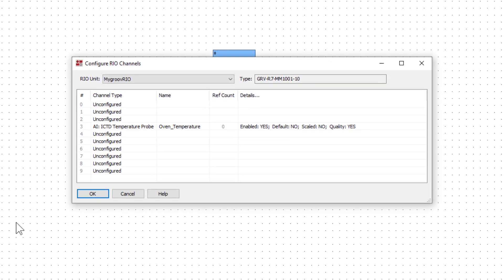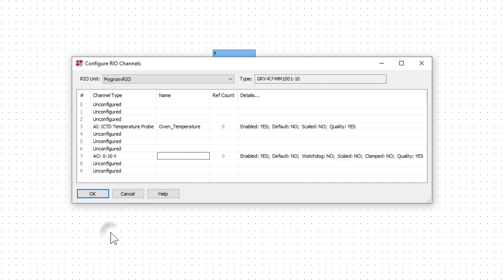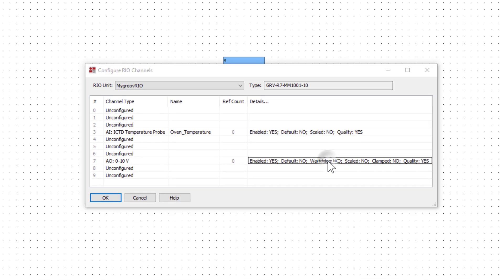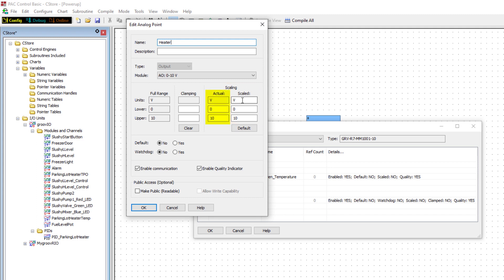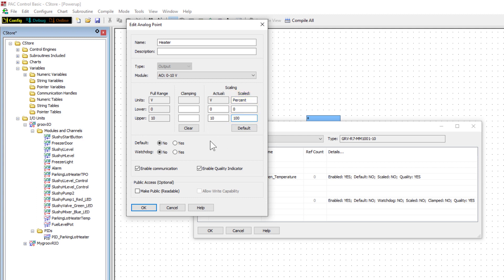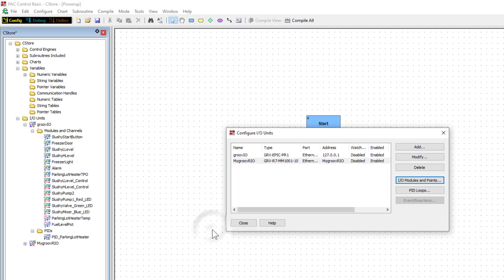Click OK to close the window. Notice the point's name appears in the name field. Click point 7 and select analog out 0 to 10 volts. Click the details box and name the point heater. From here, you can scale the point with engineering units. In this example, actual will be 0 to 10 volts and scaled will be percent for the units. Lower is 0 and upper is 100. Next, give this point public access to be able to read and write to it. Click OK and click OK again to finish configuring points.